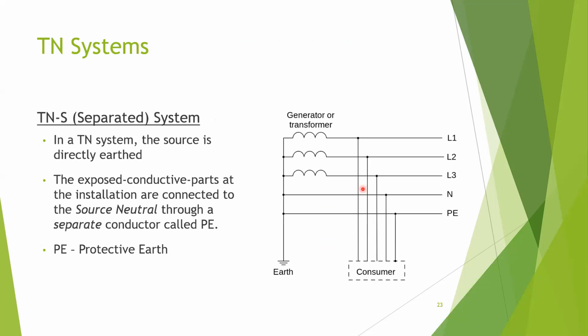Okay. Now the second one, TNS system. TNS system is the most safe earthing system, and the most expensive. In Sri Lankan distribution systems you usually have 4 wires in distribution lines. But in TNS systems, you have 5 wires because they provide a separate wire which is connected to the source earth in the distribution cable, distribution path or the distribution tower. The purpose of that wire is only for connecting to the load enclosures, the exposed conductive parts. So this is one of the most expensive earthing systems, but very safe.